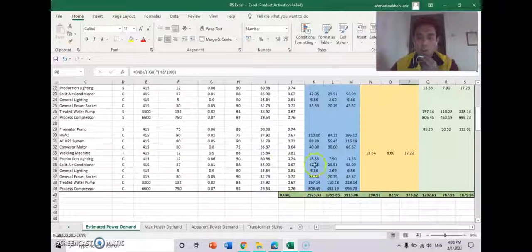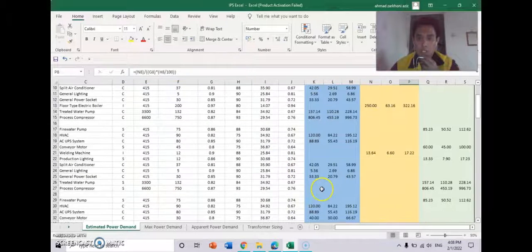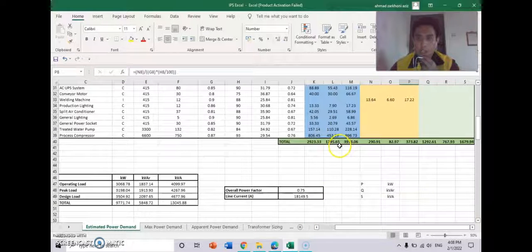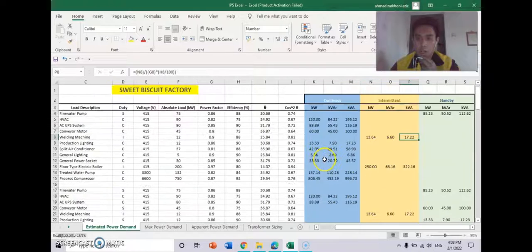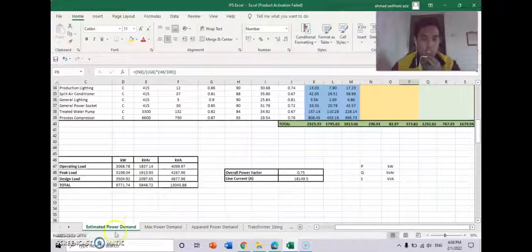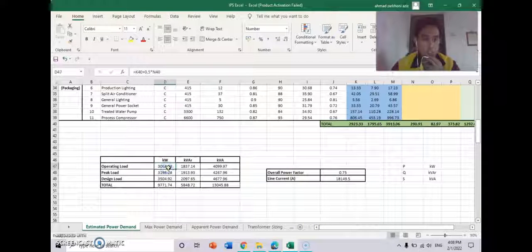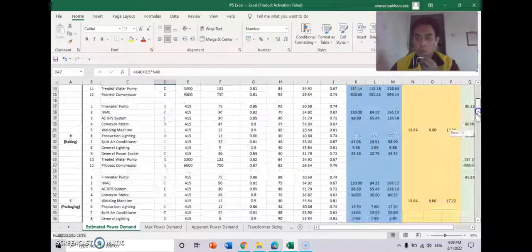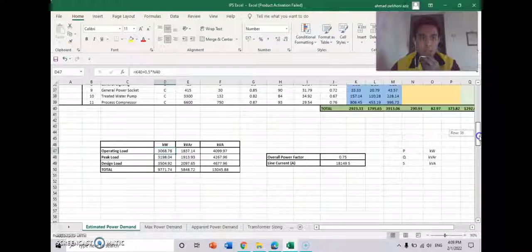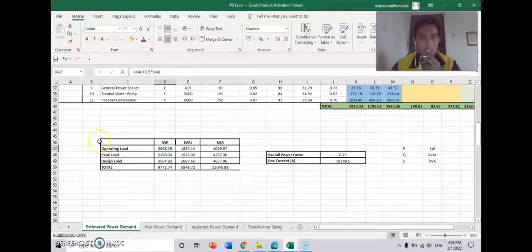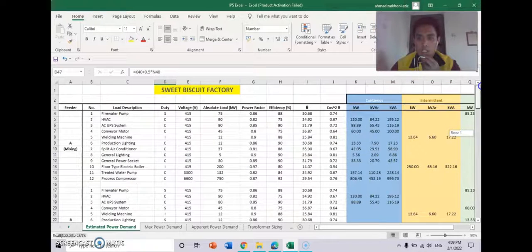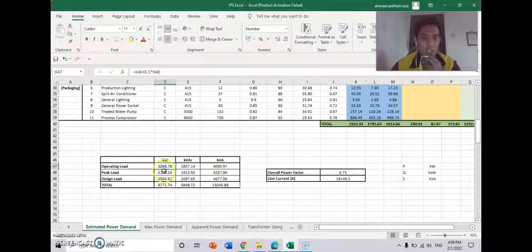This is the total amount for continuous, intermittent, and standby in kilowatt, kVAR, and kVA. So this is the operating load. The operating load uses this formula: 0.3 times N40, where N40 is 290.91, which is from intermittent kilowatt, plus K40, where K40 is kilowatt continuous. So we will get this operating load in kilowatt.